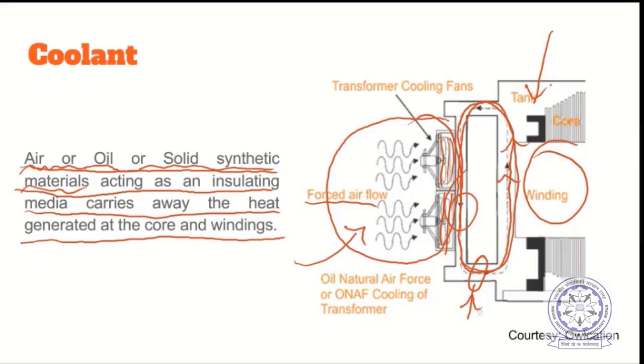Or if you use a pump, that is again forced cooling. But there are two systems you can understand here. One is the internal cooling system and the other is the external cooling system. There is an internal coolant and an external coolant here. So this is what is known as the ONAF cooling system. Oil natural, air forced. Oil natural corresponds to internal, and air forced corresponds to external. I will go into much more detail on this nomenclature in a few slides.